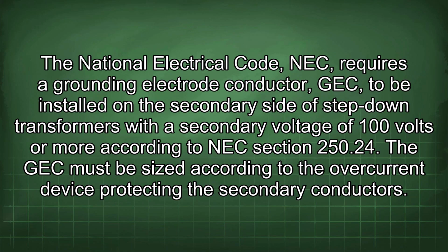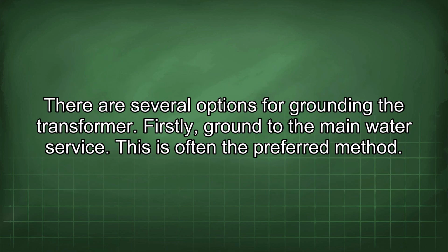The National Electrical Code (NEC) requires a grounding electrode conductor (GEC) to be installed on the secondary side of step-down transformers with a secondary voltage of 100 volts or more, according to NEC section 250.24. The GEC must be sized according to the overcurrent device protecting the secondary conductors. There are several options for grounding the transformer.